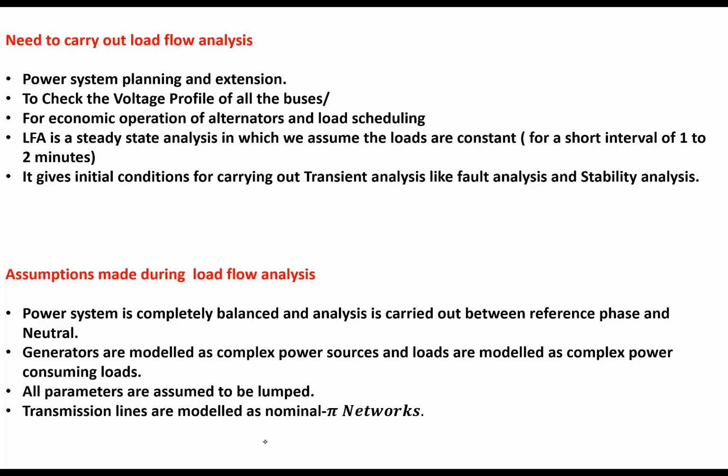We can check whether all the buses are maintaining their proper voltage profile, whether the voltage values for the existing loads are within plus or minus 6% of their nominal values. If any bus has a low voltage or over voltage problem, we can take the necessary corrective actions. So, to check the voltage profile of all the buses.